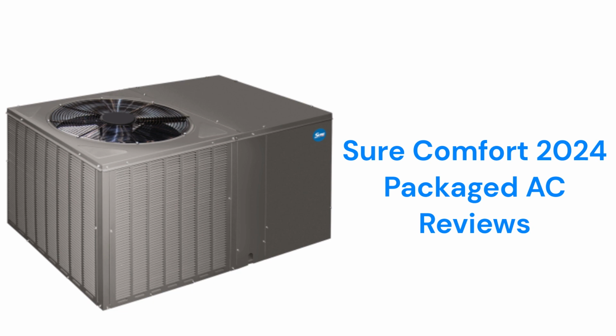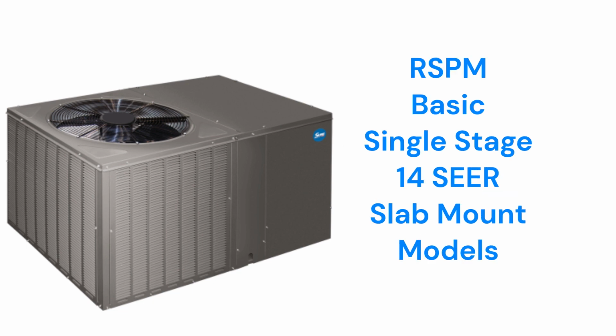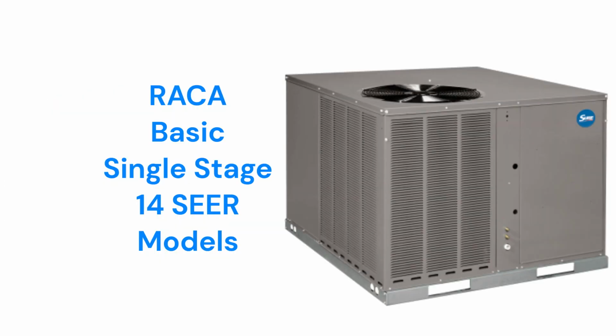They offer optional electric heat kits in sizes from 5 to 15 kilowatts to provide central heating, but they are somewhat noisy with a sound rating of 76 decibels. The RSPM 14 SEER models are for slab mounting with horizontal air discharge, while the RACA 14 models can be installed on a roof, down discharge, or on a slab.